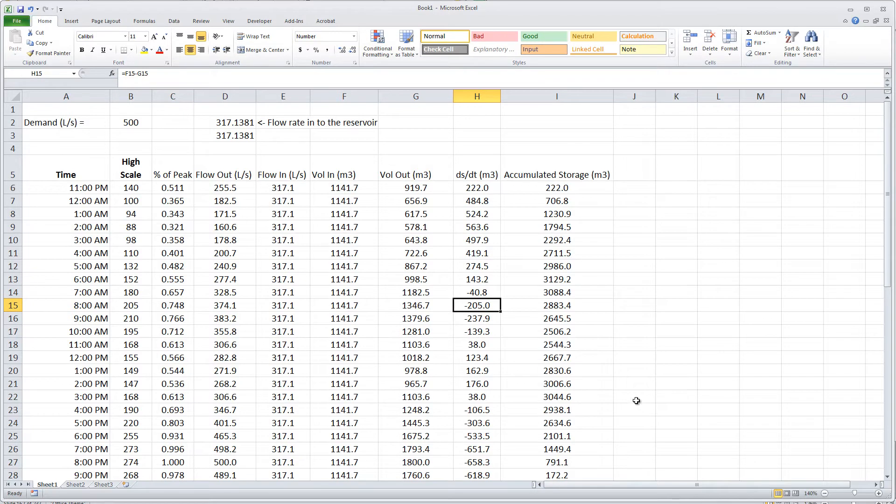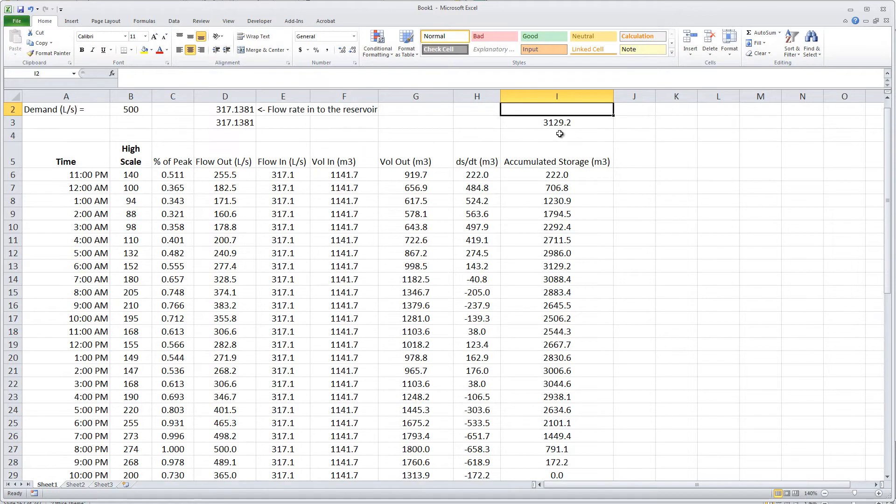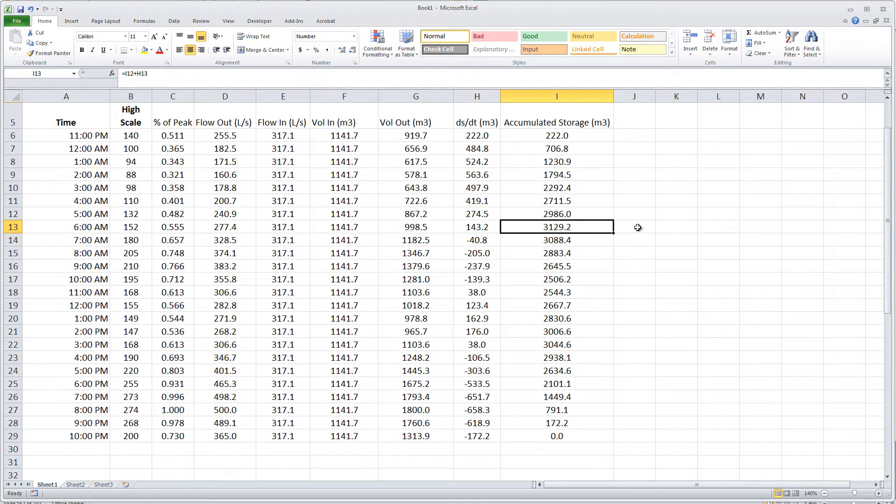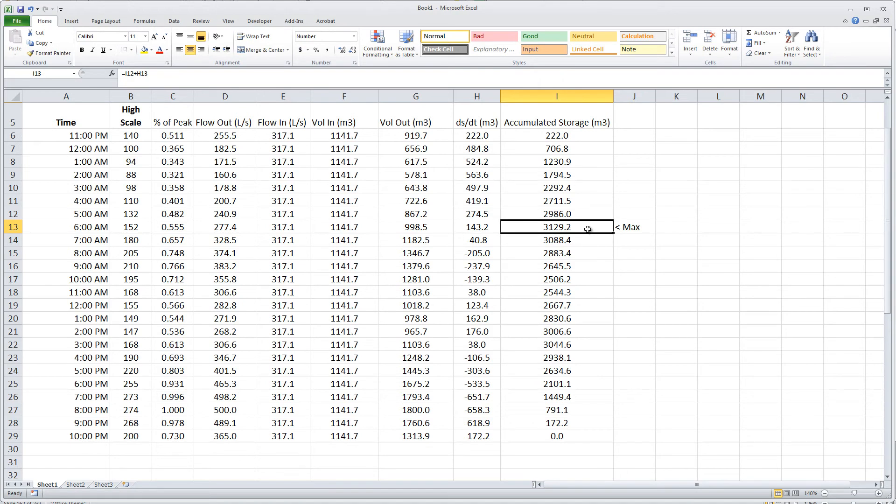So what that means is the tank is filling and it's emptying. What I'm looking for is when is it the largest during the day. What is the max of all of these? It says here 3129, so I go through and I find when is it 3129. There it is. So this is the max, this is the maximum amount that's required during the day. Therefore, my reservoir should be at least this big. I might want to offer a little bit of a safety factor, but it has to be at least this big to hold all the water that has to be stored.